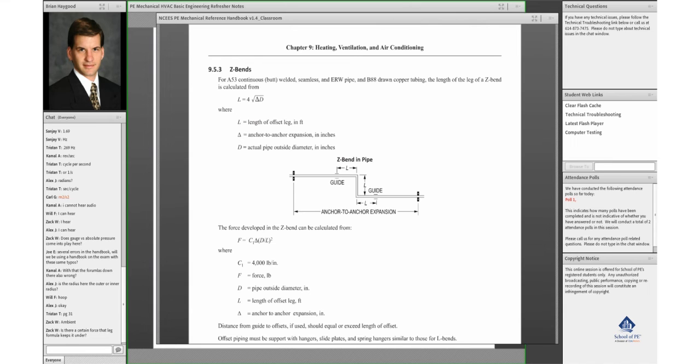If you don't want to do an L bend, because you're not making a 90-degree turn, well, maybe you want to make a Z bend, so your pipe can continue on roughly in the original direction. So again, we can calculate L. Notice the symmetry implied here. We've got a guide that's distance L back from the corner. We've got a middle length here of L, that's the same distance, and the same distance here again. So there's some symmetry suggested in your placement of these guides.